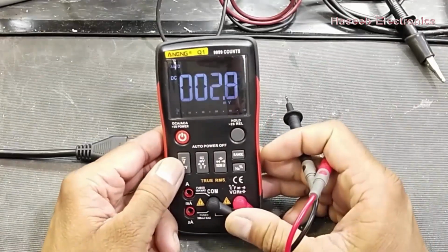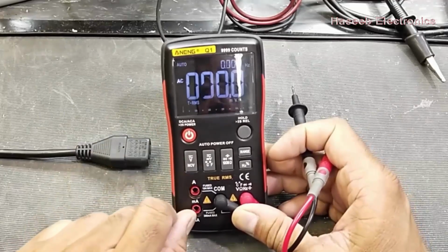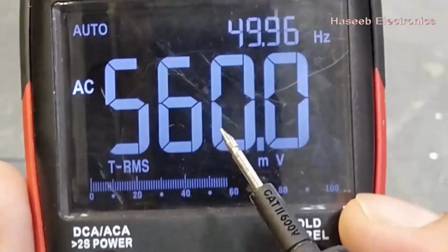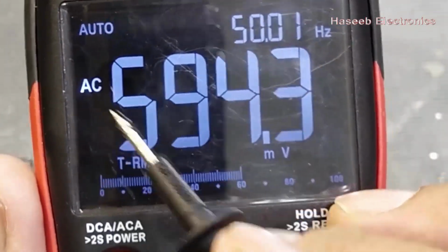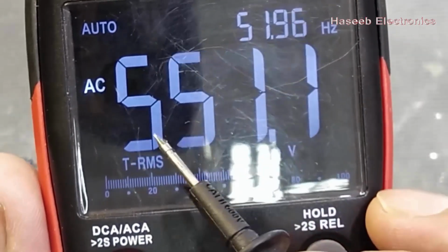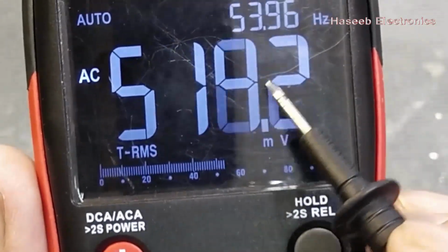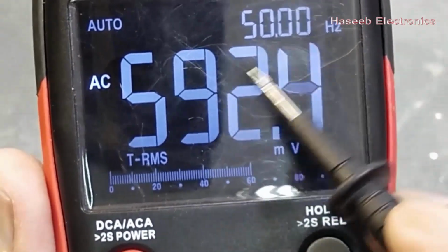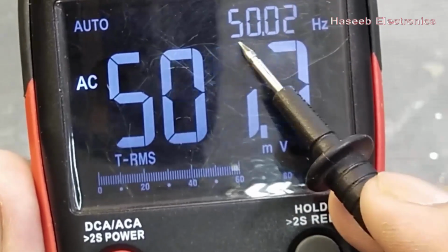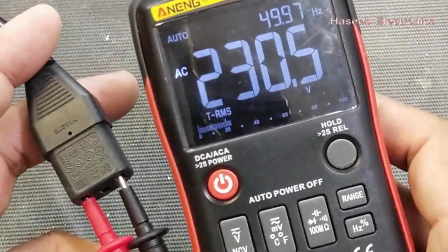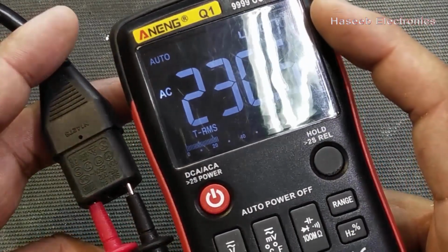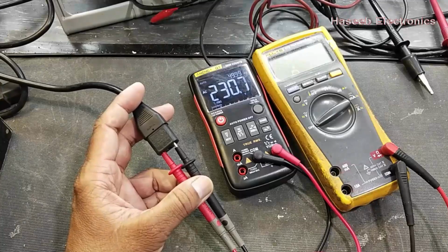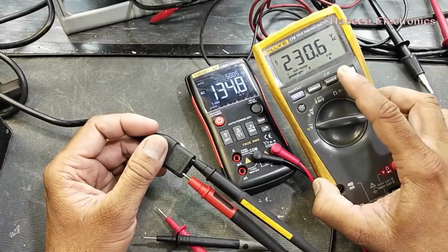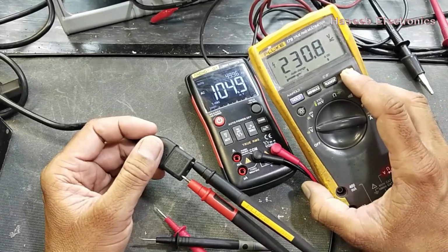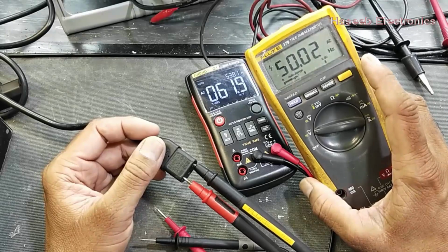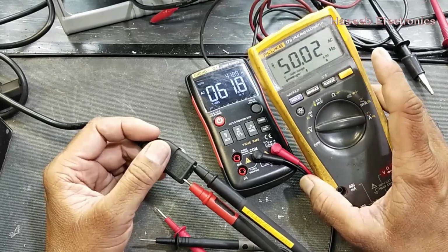Now it is DC range. I have to press this button again to switch in AC range. For measuring AC voltage, it displays auto range AC. Here we have analog bar graph, and here we have digital display, and we have secondary reading here. Here we will find voltage, and here we will find frequency. That is wonderful. It is giving 230.5 volt, 49.97 hertz. If we compare the second multimeter, 230.6, and then we have to go to the frequency mode. It is 50.0 hertz. So that's good.